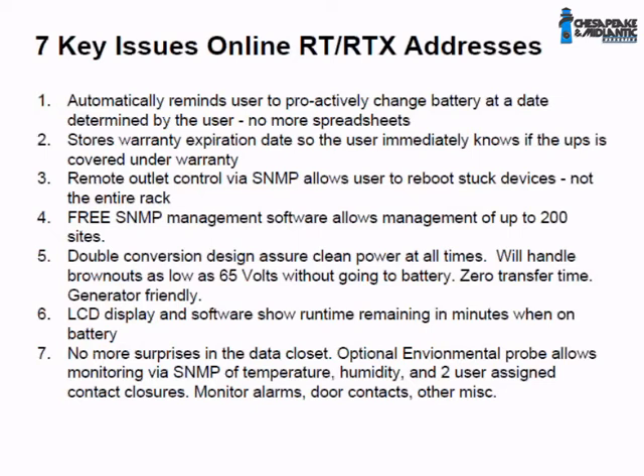The main difference is the RT does not allow you to add battery packs, while the RTX allows up to 4 external battery packs. Each module takes up 2U of rack space, and the battery packs are intelligent. When you install one, you run a networking cable from the battery pack to the UPS. As you load battery packs, the system recognizes them and adjusts the runtime calculation automatically. Other products require you to manually program how many battery packs are on the system, which becomes pretty laborious if you've got 100 units installed.